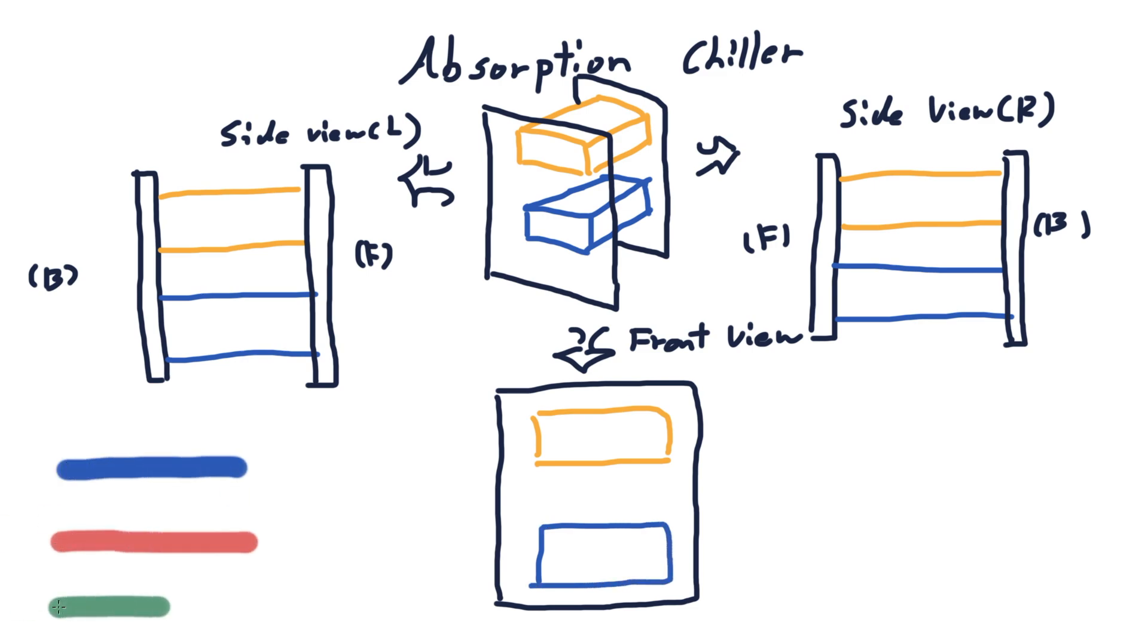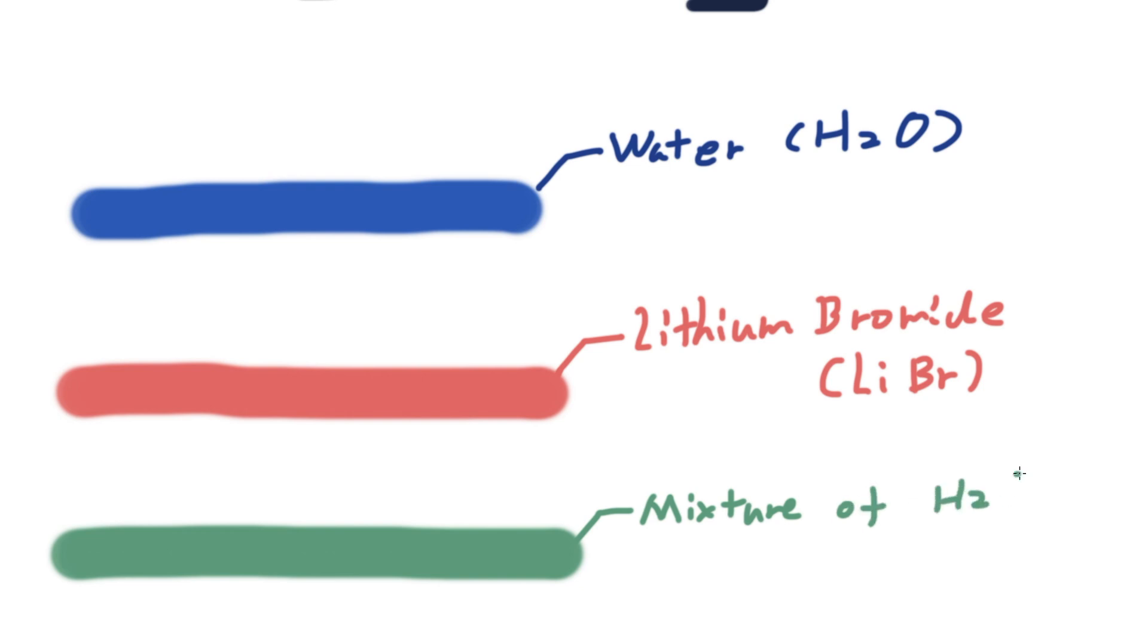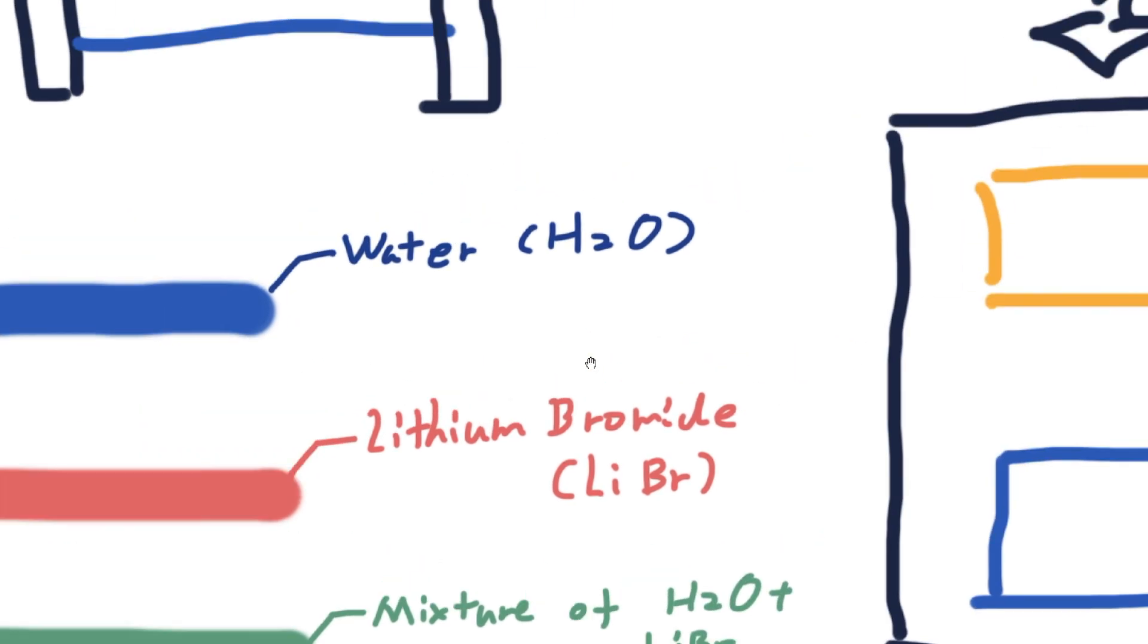Three different types of thermal fluid are used in this machine. The first is water or H2O, and the second is lithium bromide. This liquid has a very strong attraction against water and has a very high boiling point of more than 1000 degrees Celsius. And the third is the mixture of H2O and lithium bromide.